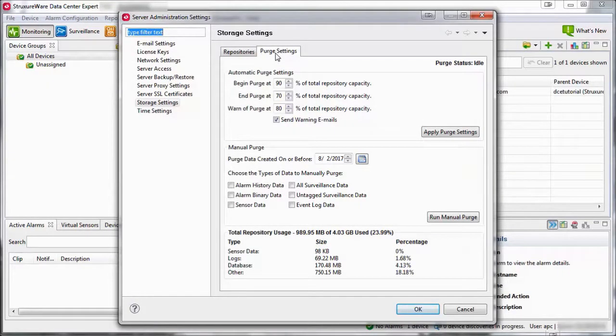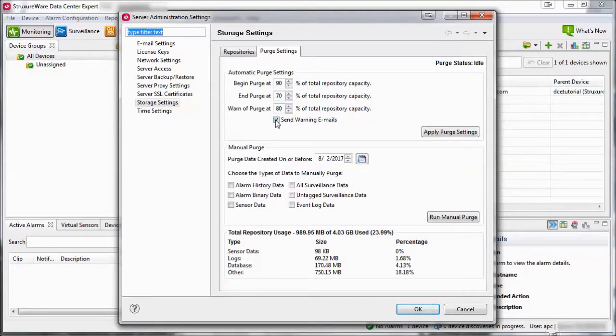Datacenter Expert will automatically purge data when a user-definable threshold is reached. It will continue purging data until the End Purge Threshold is reached. When a Warn of Purge Threshold is reached, an email can be sent out to the Datacenter Expert Server Administrators that include an email address as part of their user credentials.